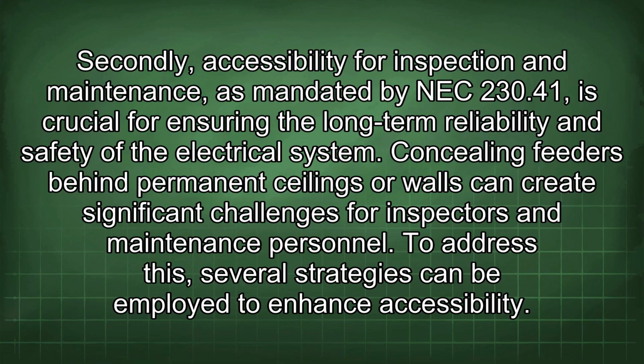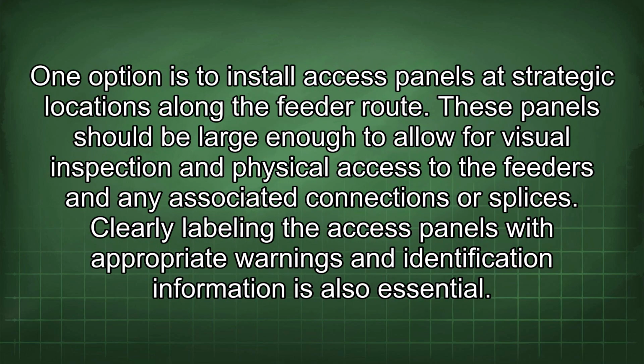Concealing feeders behind permanent ceilings or walls can create significant challenges for inspectors and maintenance personnel. To address this, several strategies can be employed to enhance accessibility. One option is to install access panels at strategic locations along the feeder route. These panels should be large enough to allow for visual inspection and physical access to the feeders and any associated connections or splices. Clearly labeling the access panels with appropriate warnings and identification information is also essential.